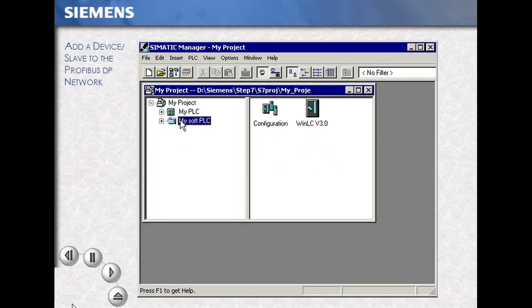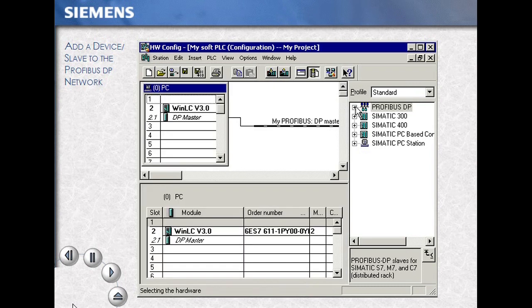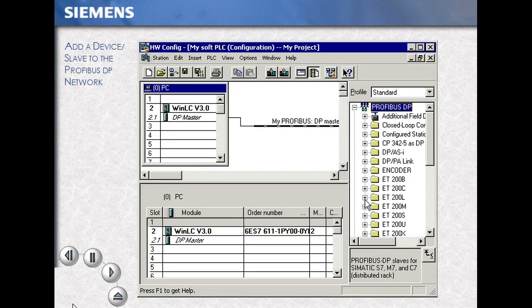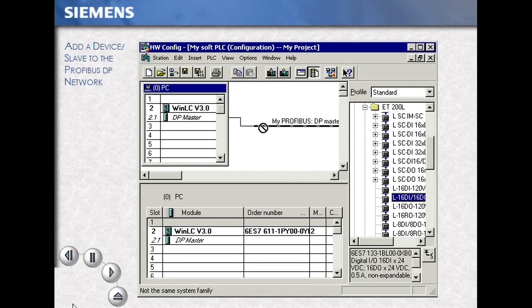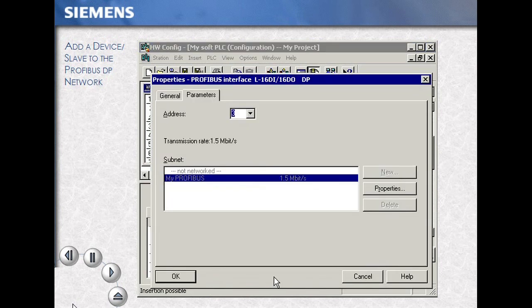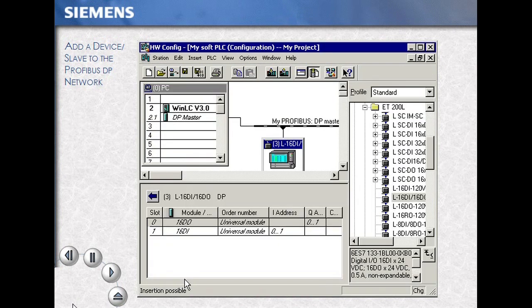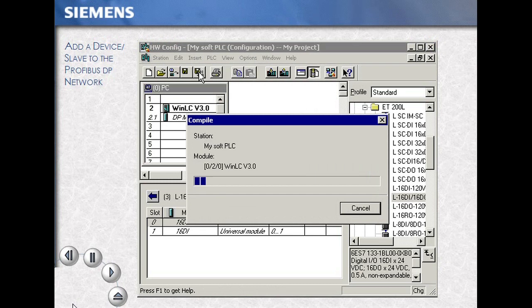Select your station, then double-click on the configuration to enter the hardware configuration. Open the Profibus DP module catalog. For this case, ET200L is the example. We are selecting a 16-digital in, 16-digital out module. Drag and drop it onto the network. OK your selection. Then simply save and compile your work. The hardware configuration automatically assigns the I/O numbering.